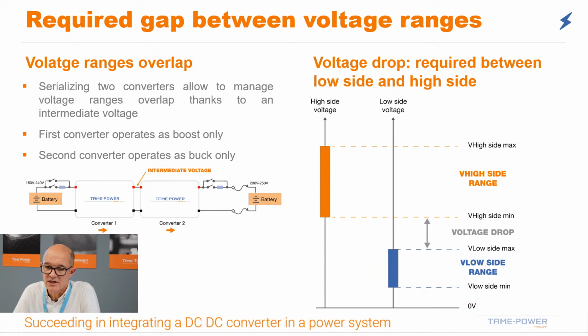In the case where your application doesn't allow this voltage drop, for example on the left side where there is a battery-to-battery system, there is an overlap between the battery on the left and the battery on the right. To assume that, we use 2 converters, so in some cases it's mandatory. In between these 2 converters, we program an intermediate voltage, so that the first converter will always act as a boost, and the second one will always act as a buck, and this will allow power conversion between two devices which need an overlap in their voltage ranges.